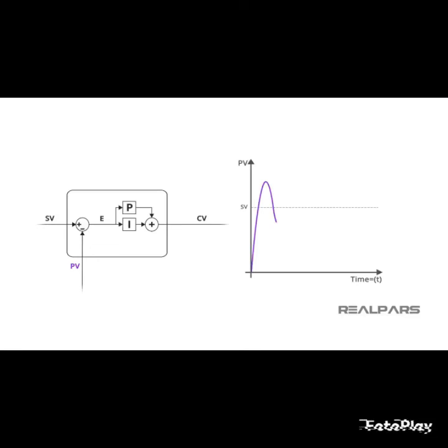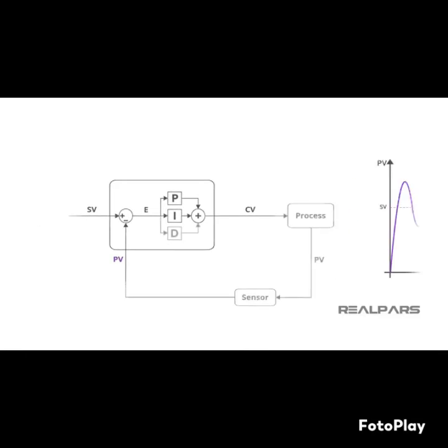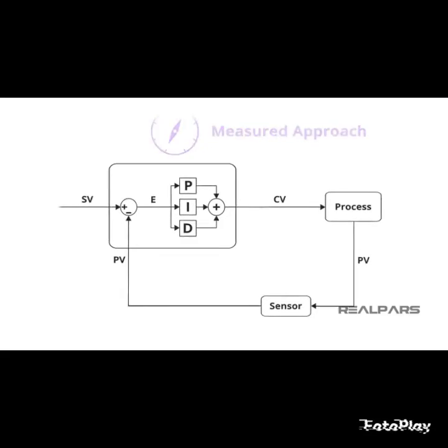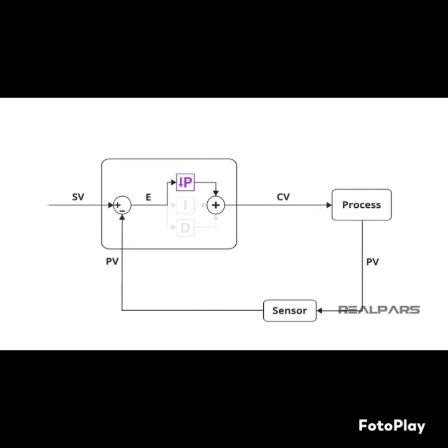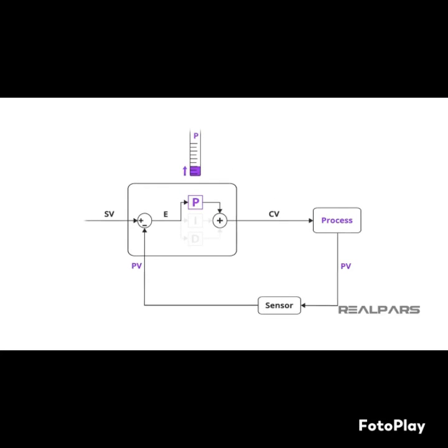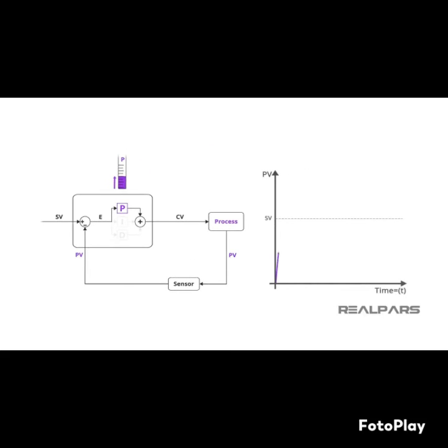A more measured approach is to start with a low gain with integral and derivative disabled. Watch the process and begin incrementally adjusting the gain by doubling the value. When the process begins to oscillate, adjust the gain value down by 50%. Employ a small integral value and watch the process. Double the value incrementally until oscillation occurs, then cut the integral by 50%. At this point, you should be somewhere in the neighborhood and can begin the fine-tuning process.